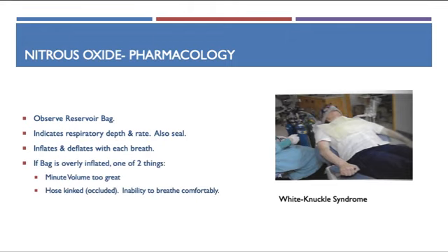Now there's a reservoir bag attached to these systems. Not only is it attached to the digital system that we use here at the school, but it's also attached to some of these portable systems. And the reservoir bag is really just a big green rubber bladder that you fill up with air. When you fill it up with air, watch the movement of the reservoir bag, because as the patient breathes, the reservoir bag should expand and contract along with the patient's breathing. If it's not doing that, then you have a blockage somewhere and you have to find where that blockage is.